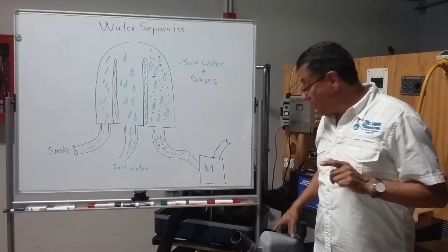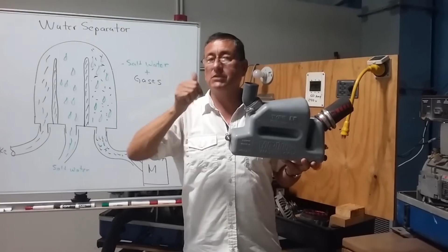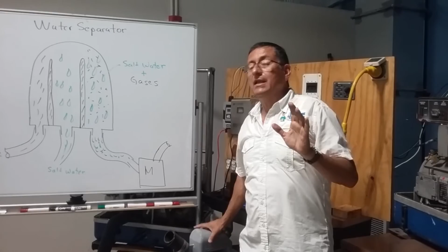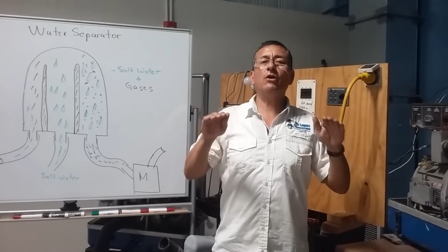All right. Important, the reference of the level of the water line. Important, the location of the fuel tank. Important, the location of the batteries. Important, where the muffler should be located. Remember, the muffler should be located below the level of the generator, minimum 2 inches, very important. The water separator, if necessary. And don't forget the anti-siphons. If my generator will be located below the water line, I need 2 anti-siphons.